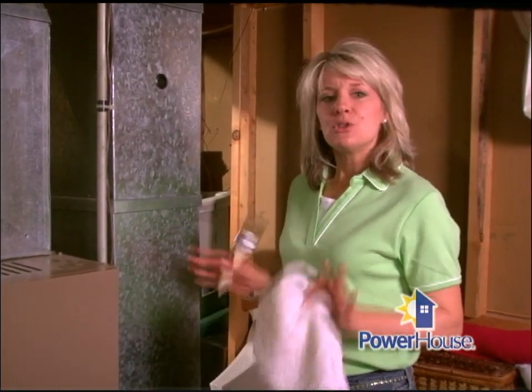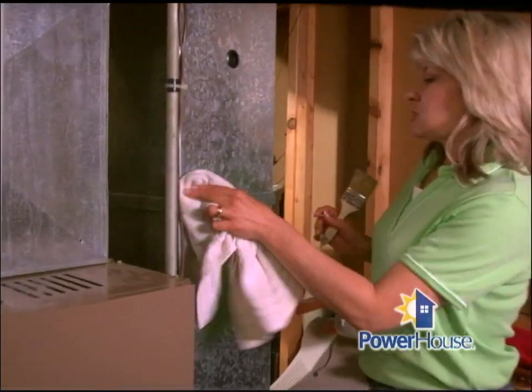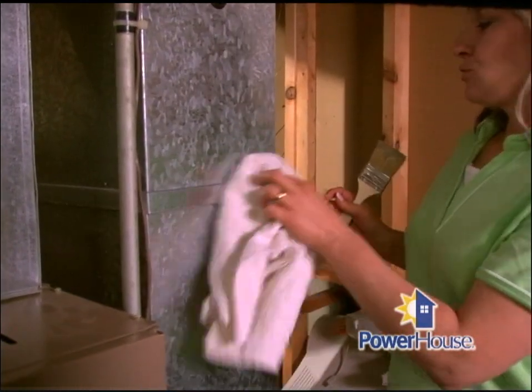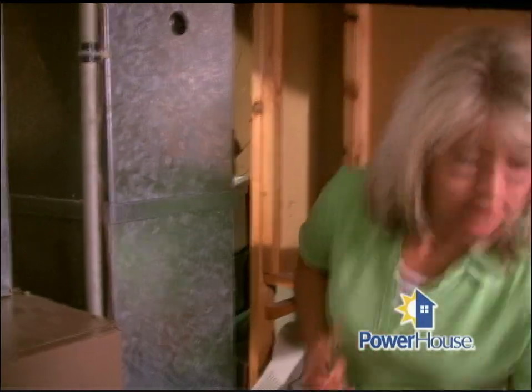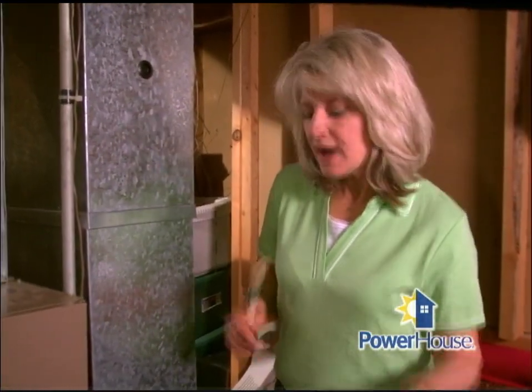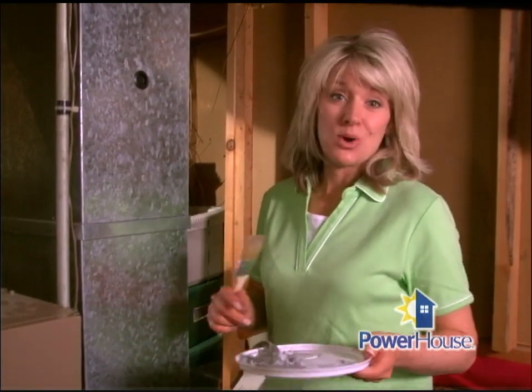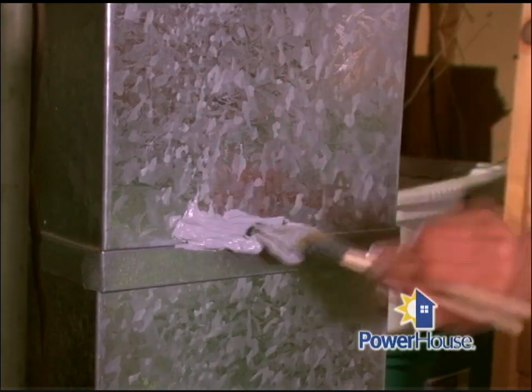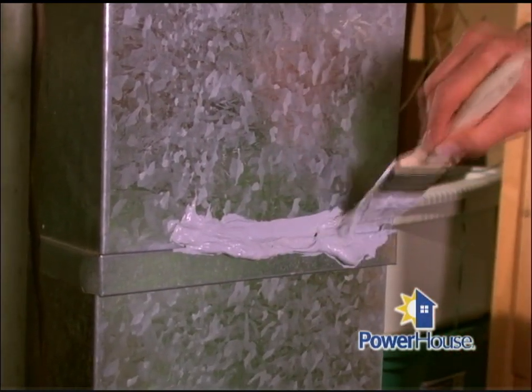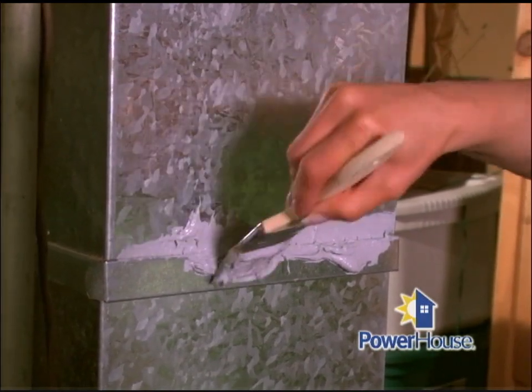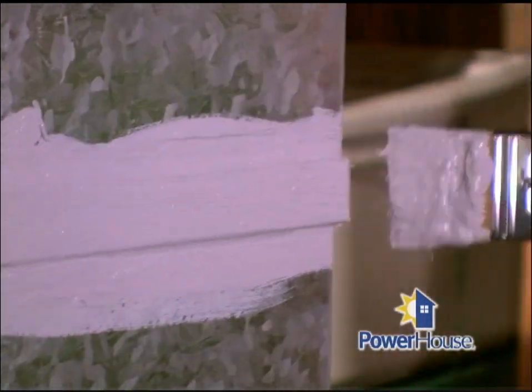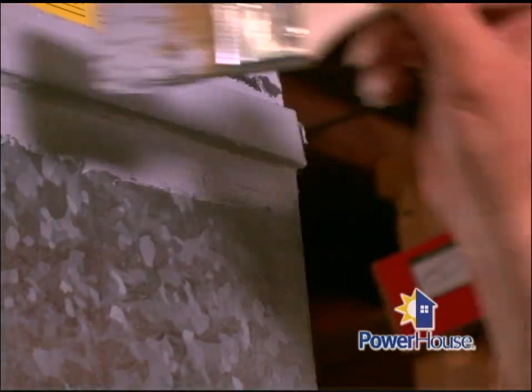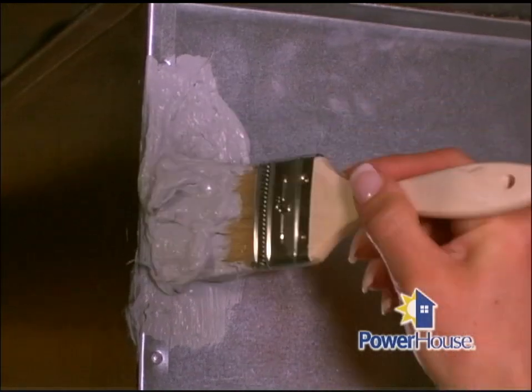Now, before applying, make sure that you wipe the joint area to remove particles, dust, and grease. Okay, like that. And you'll also want to make sure that you cover the floor and any area around the ducts with a drop cloth as well. Apply enough mastic to form a continuous coating on the surface of the duct and work the mastic into the joints or cracks. Then use light pressure to get an even coating. There should be at least a 1/2 inch overlap around any joint, crack, or hole. You should also allow the mastic to dry completely for 24 hours, which means not running your furnace or air conditioning during this time. You might want to do this project during a time of the year with mild temperatures.